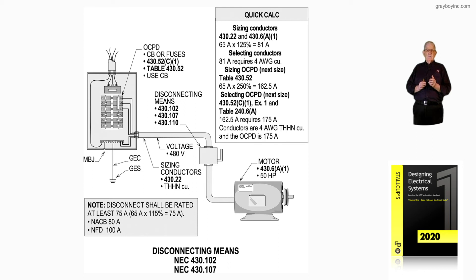CB and the panel board ahead of number four conductors feeding the motor. Say the nameplate on the motor was 62 amps, not 65 which is the table current, but the nameplate is 62 amps. Electricians that I've known, engineers that I've known, if they don't have a code book handy and they're out in the field, they'll just take that 62 amps on the nameplate, round it up to an even unit number of 10, which would be 70. For code letters A through G, most of all you're going to have B or C or D. For code letter B, C, or D, safely you can say six times. So rounding 62 nameplate up to 70 times six is 420.